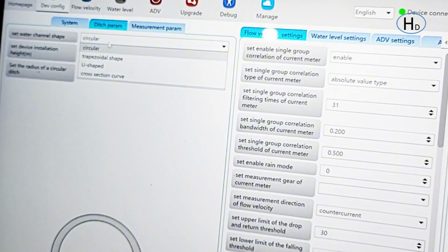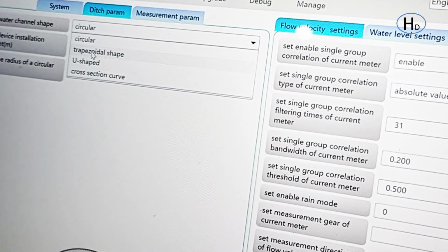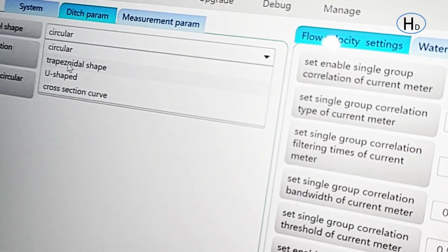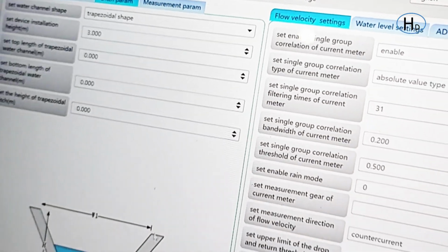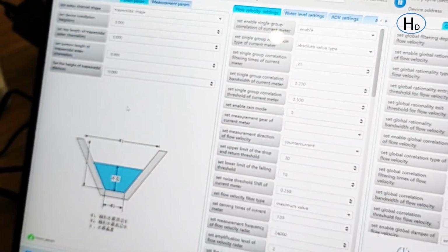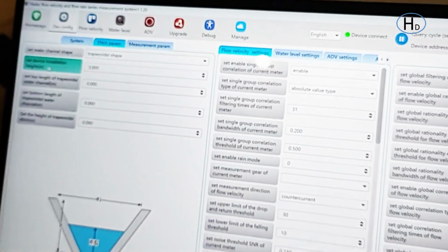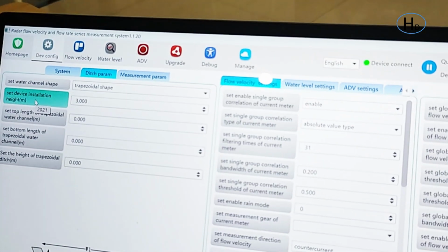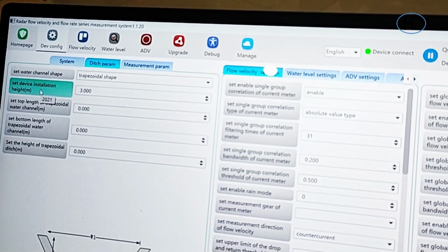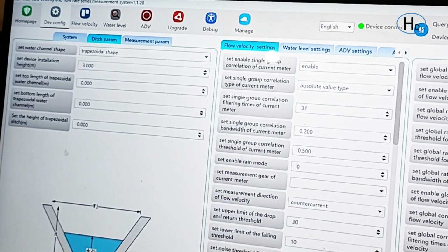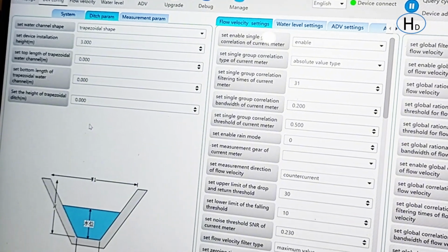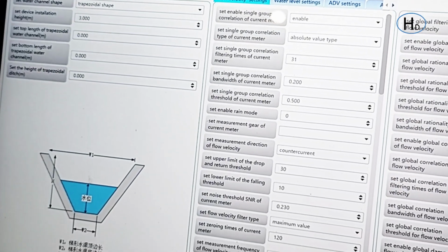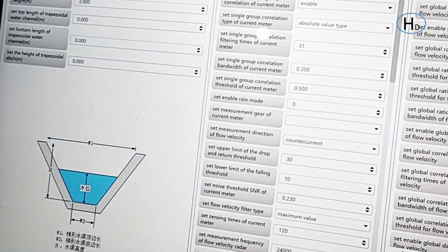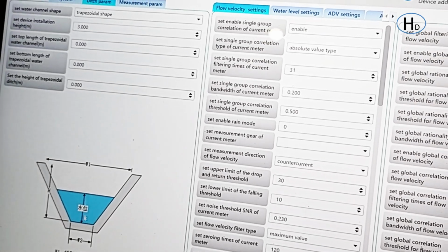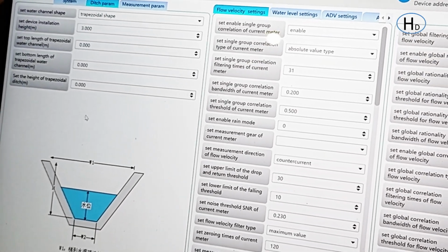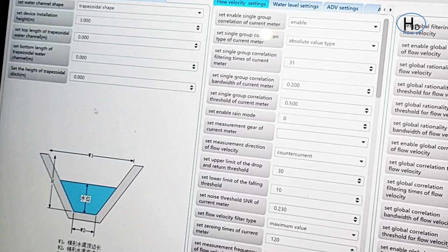And if your open channel is a trapezoidal shape, then it will change. What you need to set is, first, also set the device install height. Pay attention to that. The installation height means, for example, you install the radar sensor here. The height is from the sensor to the bottom of the channel. That is the install height. So this depends on your real condition.